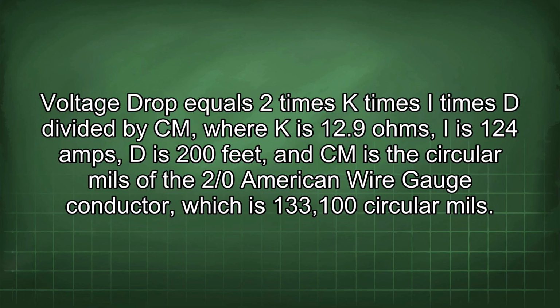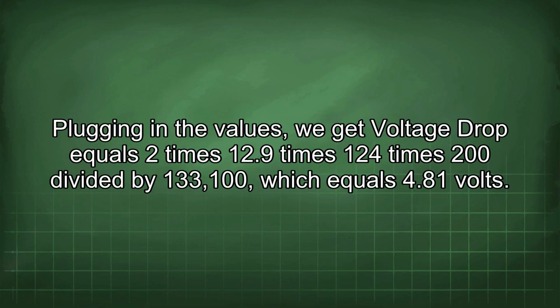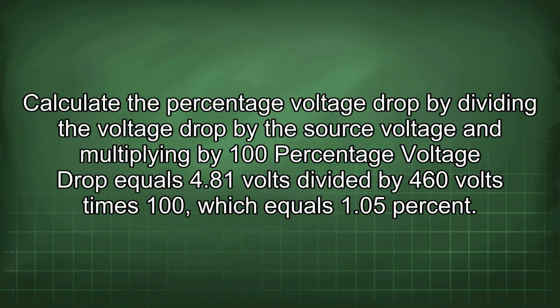133,100 circular mils. Plugging in the values, we get voltage drop equals 2 times 12.9 times 124 times 200 divided by 133,100, which equals 4.81 volts. Calculate the percentage voltage drop by dividing the voltage drop by the source voltage and multiplying by 100.